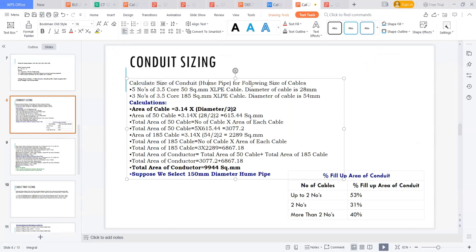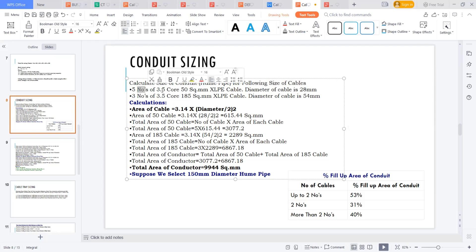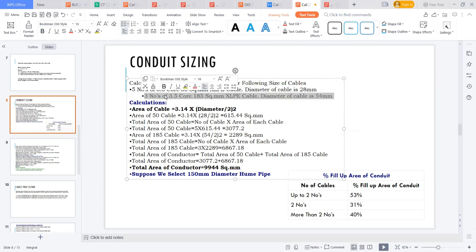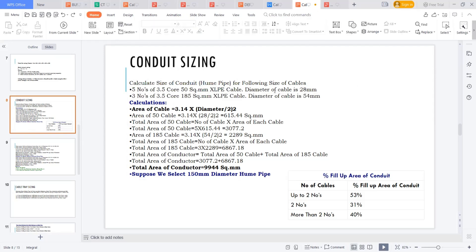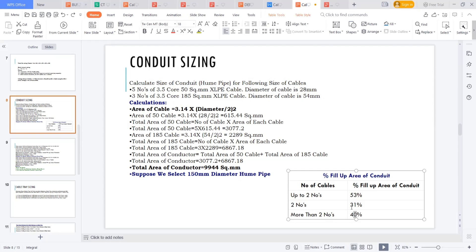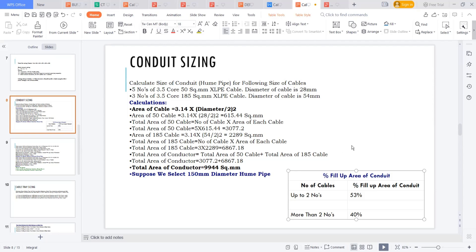Calculate the conduit size for the following: five numbers of 3.5 core 50 sq mm cables with 28 mm outer diameter, and three numbers of 3.5 core 185 sq mm cables with 54 mm outer diameter. The fill-up area rule is: up to two cables — 53%; more than two cables — 40%, to avoid jam ratio when pulling the cables.